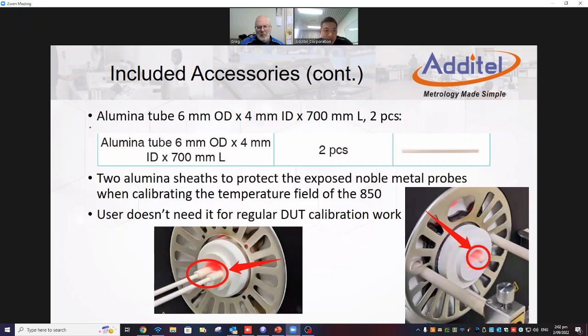So we have another kit of the alumina tube. This is for the reference probe. As I said, most of the noble metal thermocouples don't have the sheath. They just come with the exposed wire or something like that. So this is the sheath to protect them. We have a 700 millimeter, that's longer than the furnace length. The furnace length is just like 680 or something.